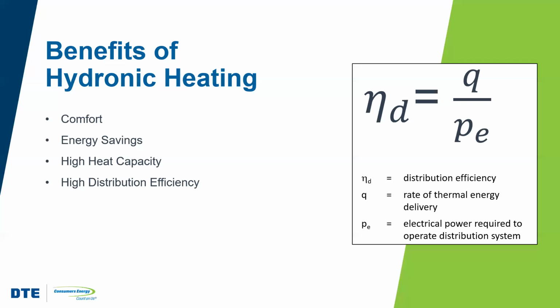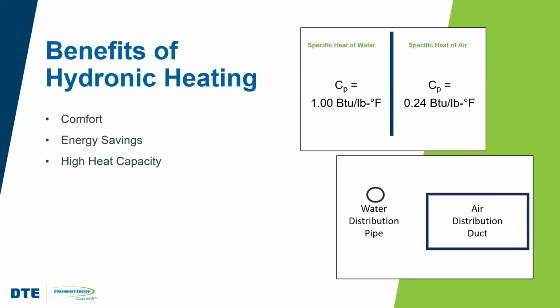This is similar to an air distribution system, right? That would be looking at the heat output and the amount of fan energy that's needed to get that air around the building, right? And so the units of the distribution system efficiency are BTU per watt per hour, right? Now, to distribute the same amount of energy, pump watts may be on the order of 10% of what a forced air system might require, right? So you've got significant distribution system efficiency there with the hydronic system.